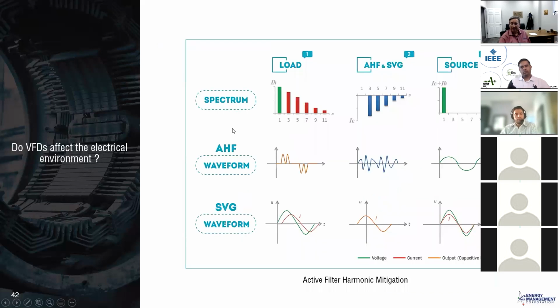The way an active harmonic filter works, you may already be familiar from noise canceling headphones. It's basically injecting noise at 180 degrees to the noise that is already there. If you had the third harmonic in a single phase load, but the fifth, the seventh, the 11th, the typical non-triplen harmonics would be injected with current at 180 degrees phase shift. That looks like a pretty nasty waveform of noise you're injecting, but the result is you convert this into this. I'm getting more and more sold on this technology for multiple reasons, but cost is not the lowest.